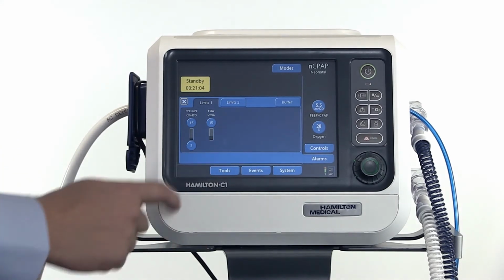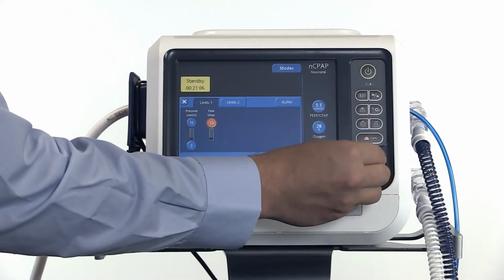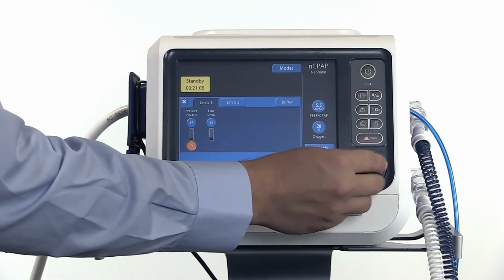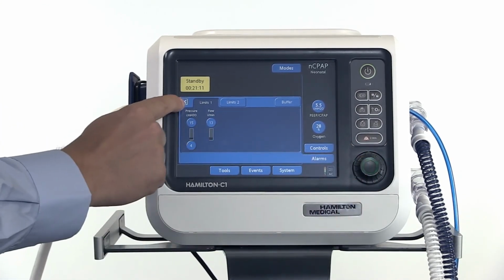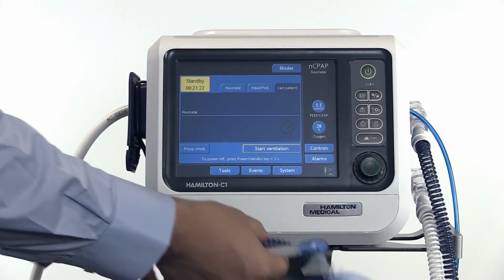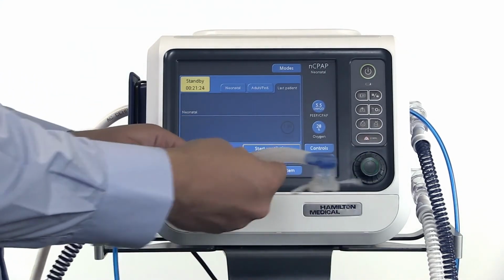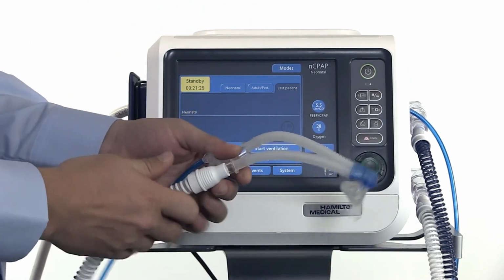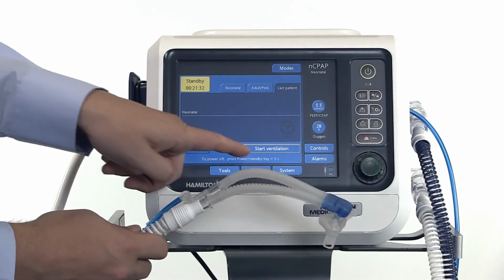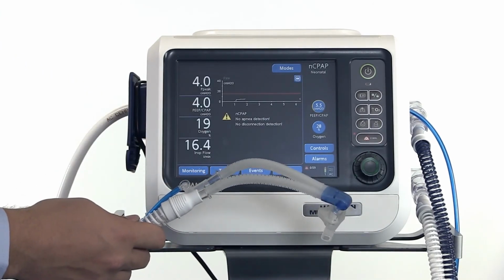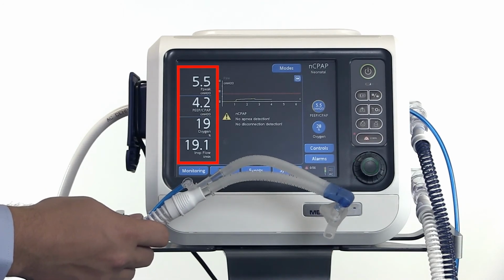Adjust the flow and pressure settings if necessary. When you have finished, close the window. Now you can connect the circuit with the NCPAP generator and then start ventilation. The NCPAP screen shows you a pressure curve and 4 monitoring parameters: P-peak, PEEP, oxygen, and inspiratory flow. Note that there is no detection for apnea or disconnection in NCPAP mode.